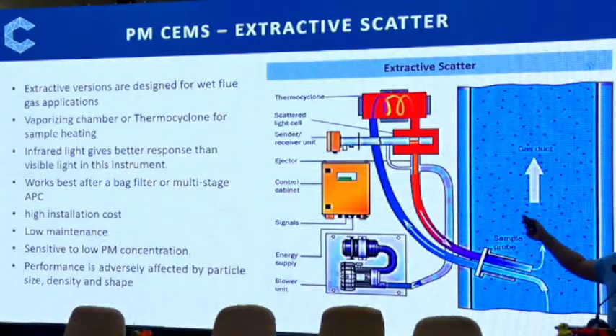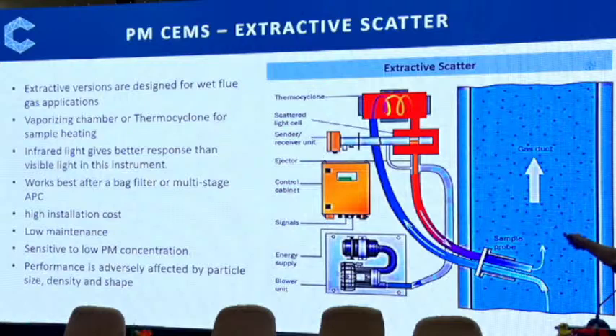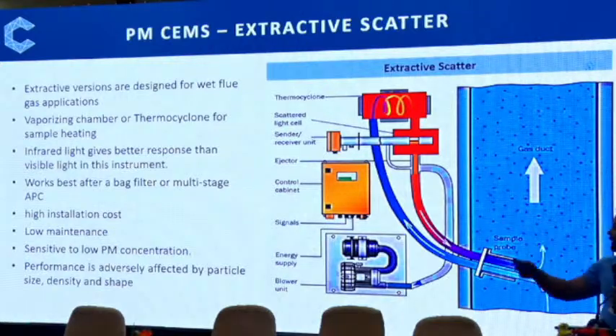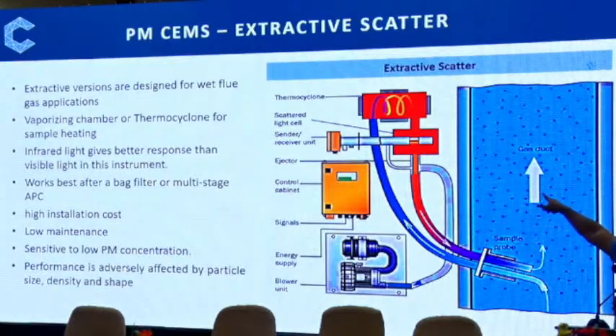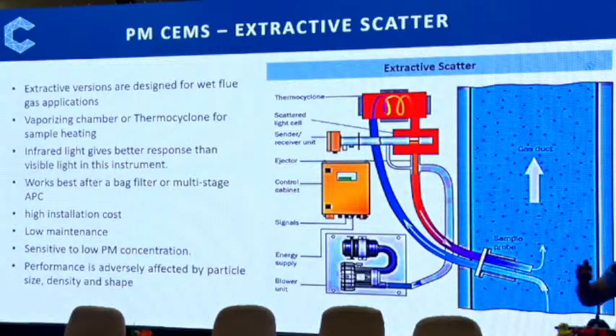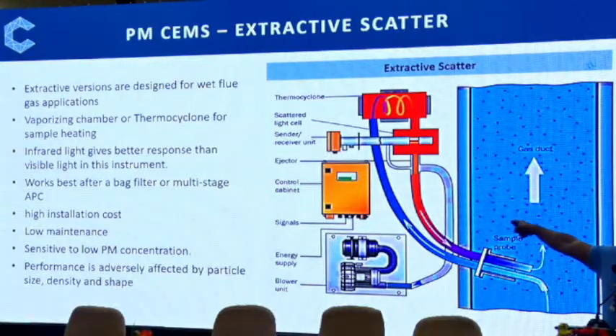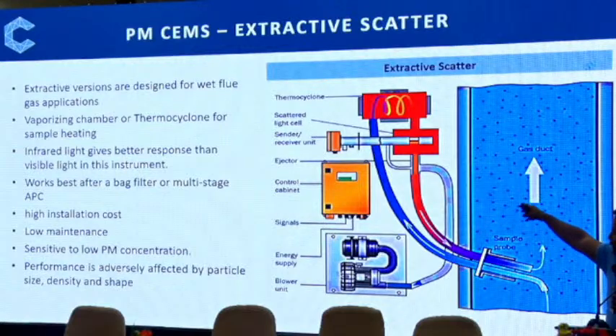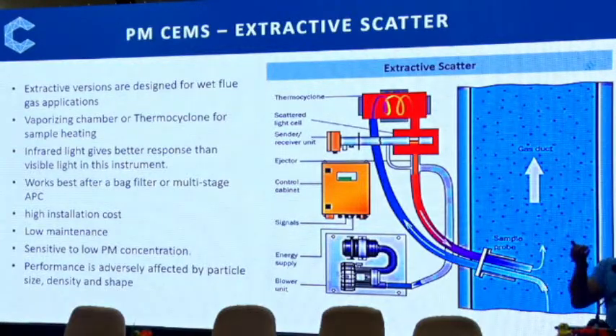What is happening here? The red line you see: sample gas is taken out. It is heated in the thermocyclone or vaporizing chamber. Literally, the water droplets which are there become vapor, not in droplet form. It will be monitored with scattering technology, normally forward scatter. It is monitored and then the gas is discharged. Once the gas is out, again there will be water and all. It is thrown out again. So this is the technology.